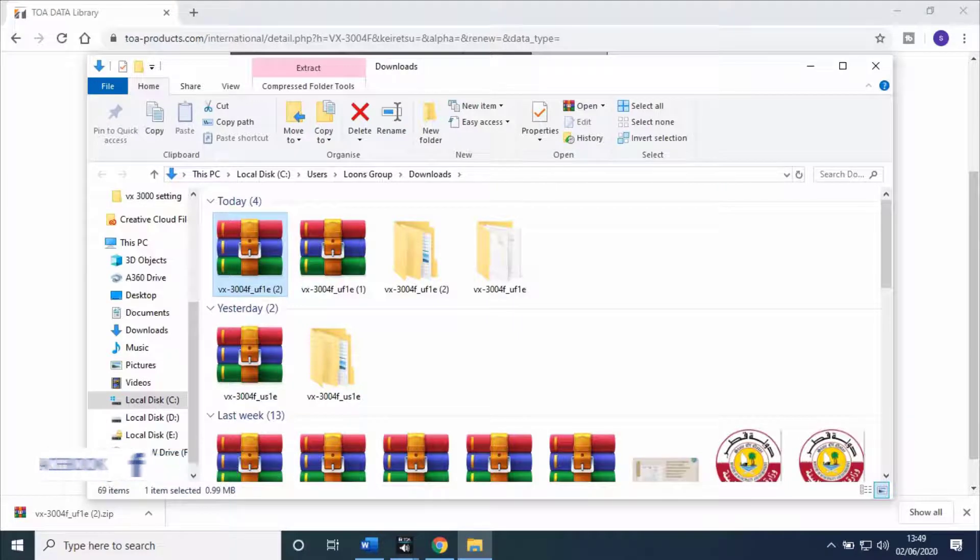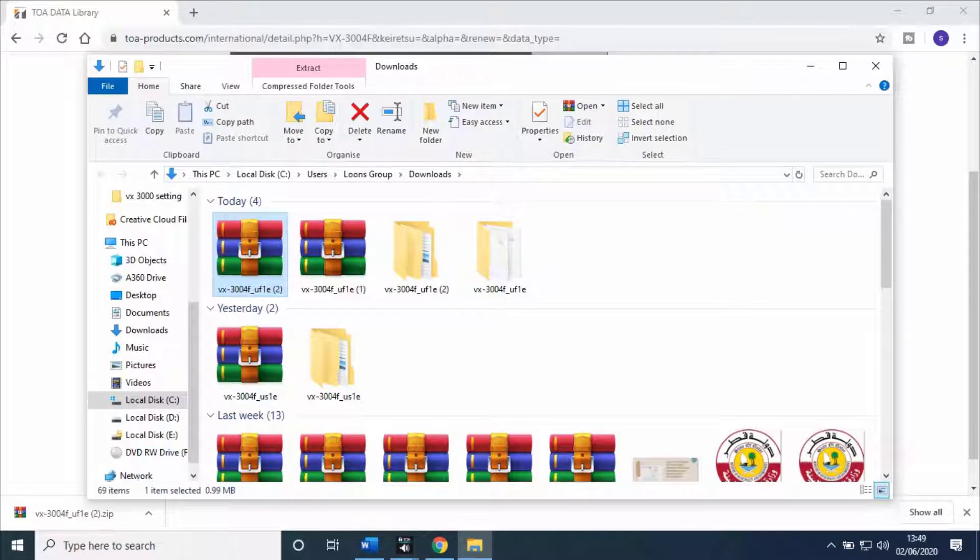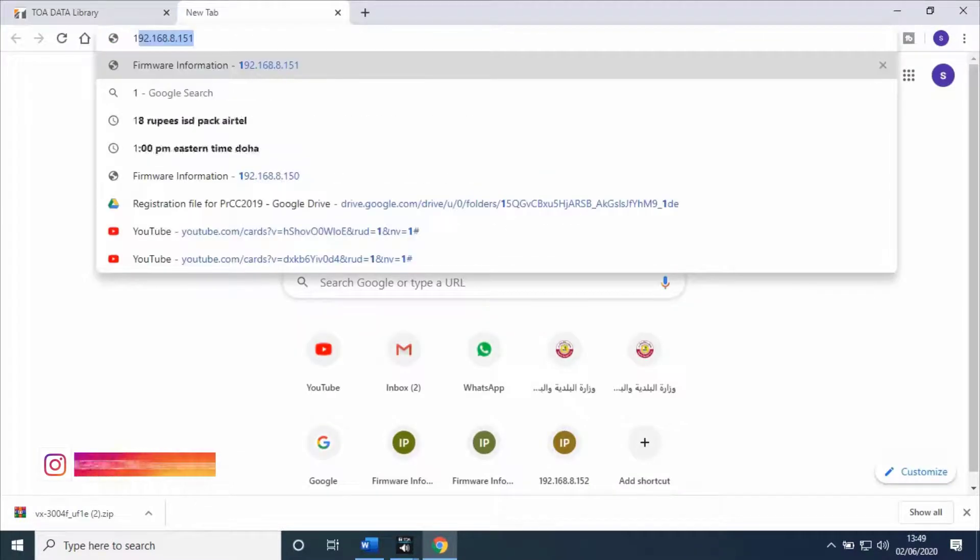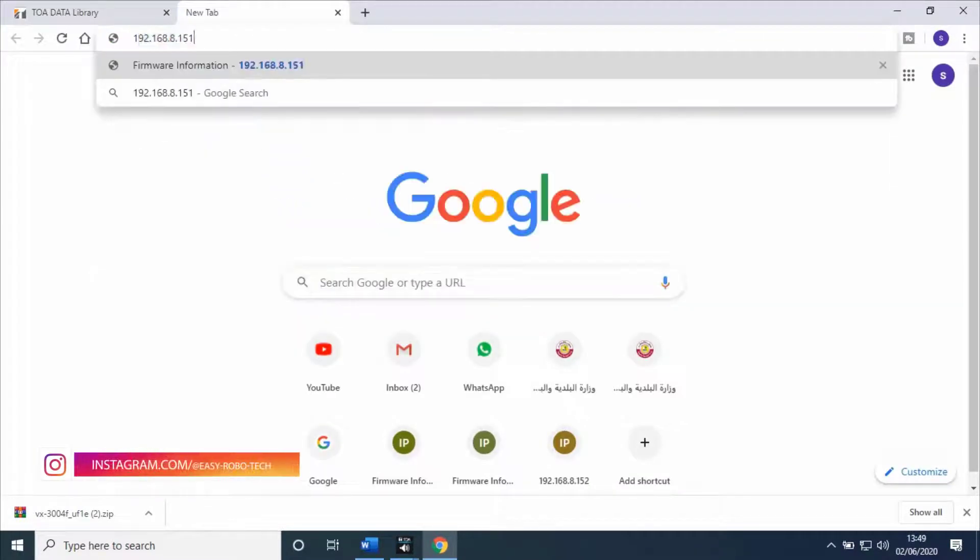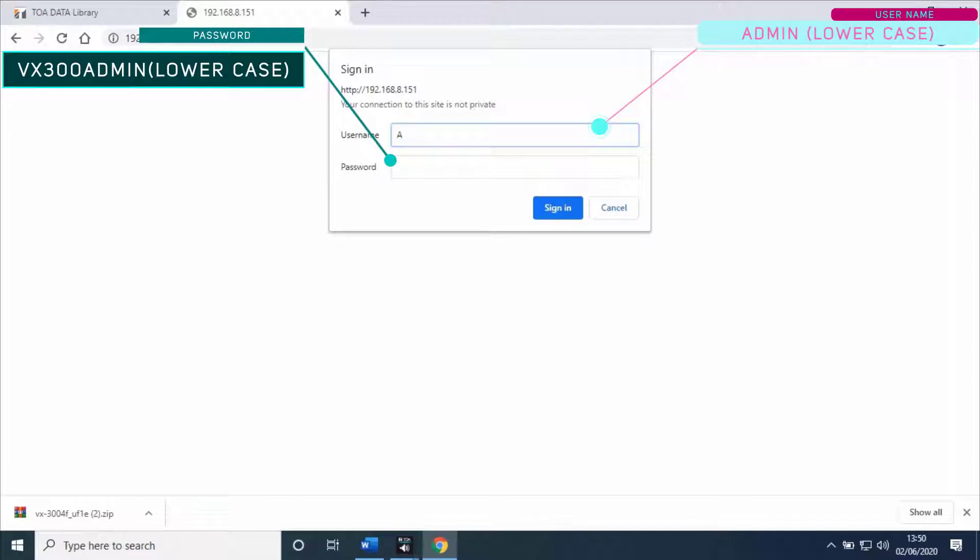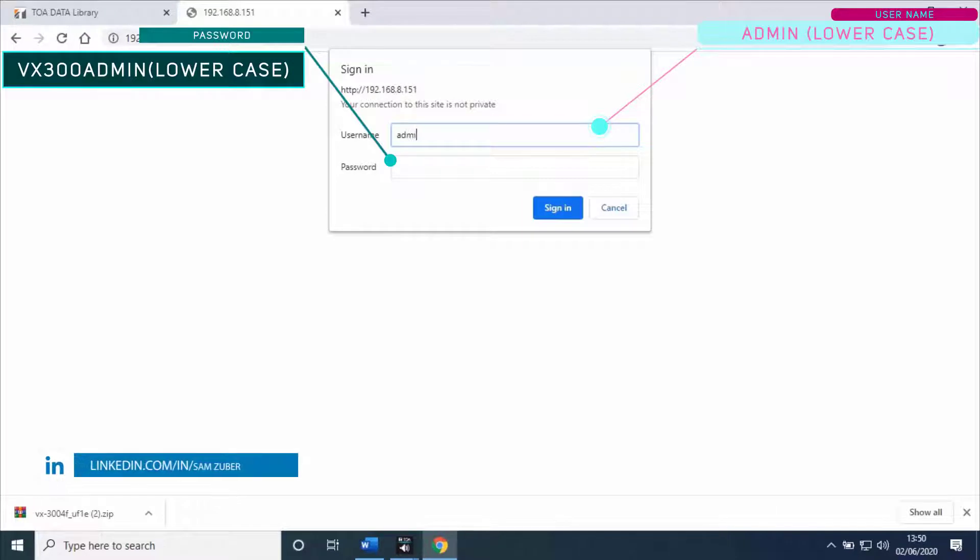To do that, go back to the web browser and type the IP address of the Voice Evacuation Frame. Type username as admin and password as vx300admin. All characters are in lowercase.